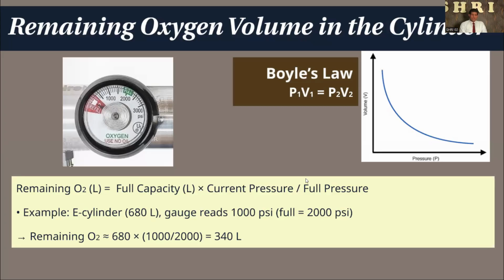If you take the E cylinder, the full capacity is 680 liters. If the pressure gauge shows 1000, that means 50%. So the amount remaining is 680 liters times the remaining pressure divided by the pressure of the total capacity, and that gives the amount of oxygen remaining in that cylinder.